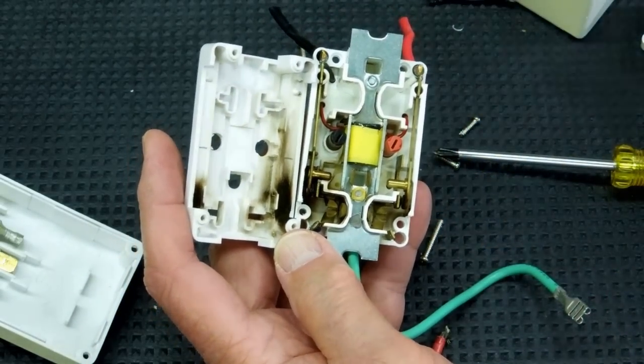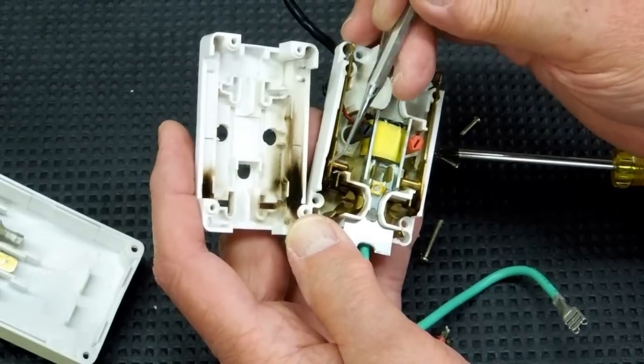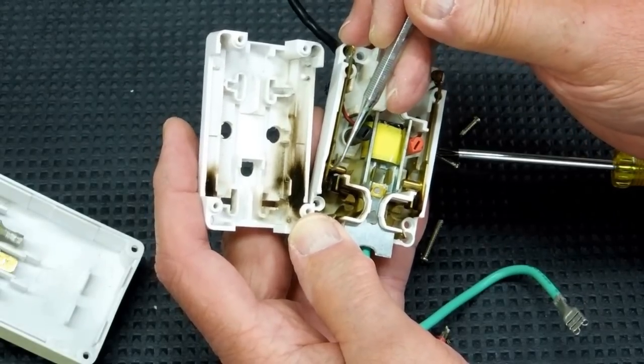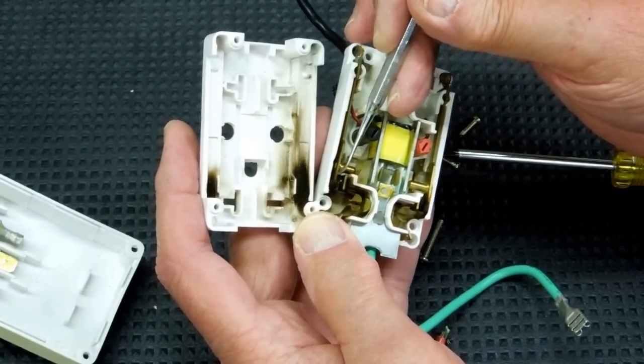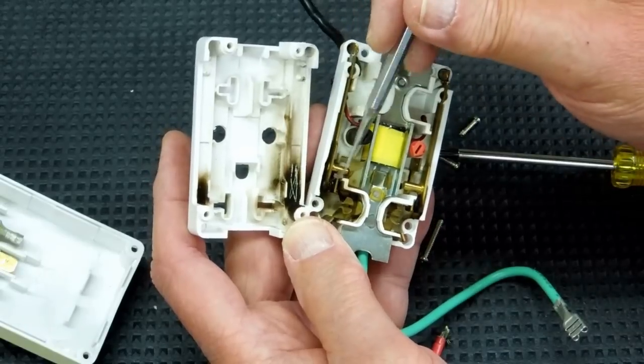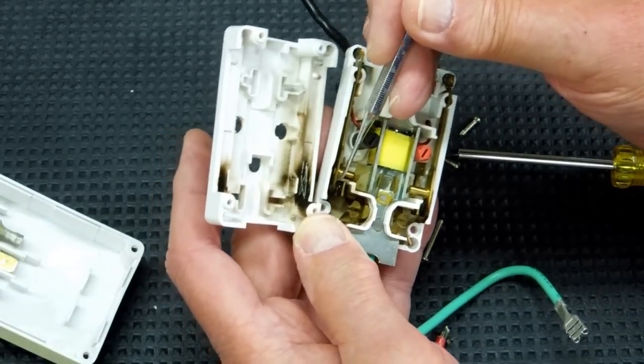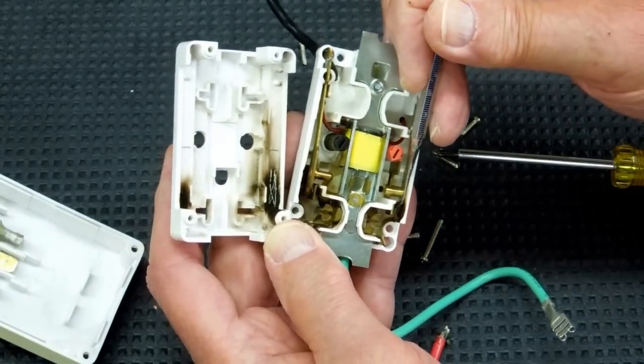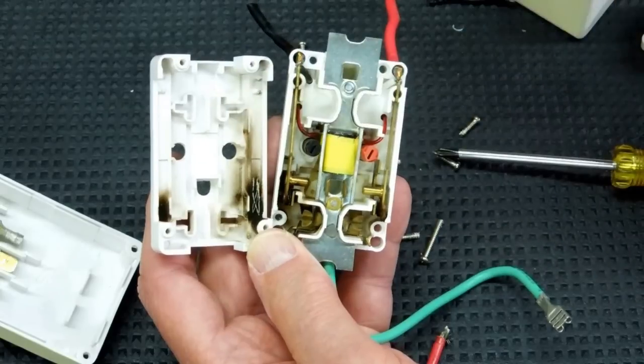This is more in line with what I was expecting to find and the way it was acting. This thing has turned on and off so many times it's flashed these contacts. They are carboned up or pitted, and that's why it would sometimes work and sometimes wouldn't.